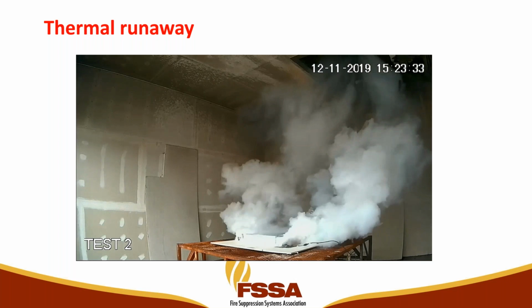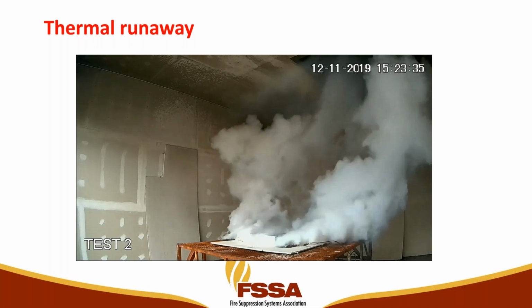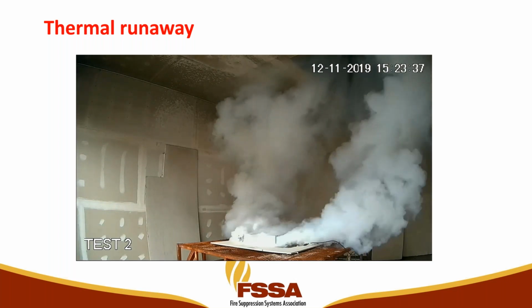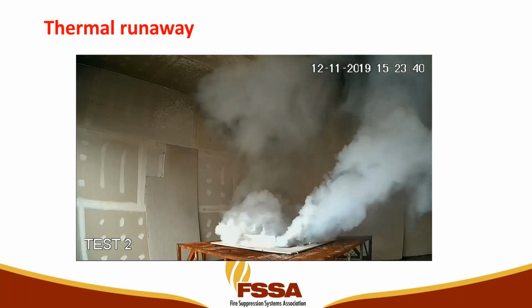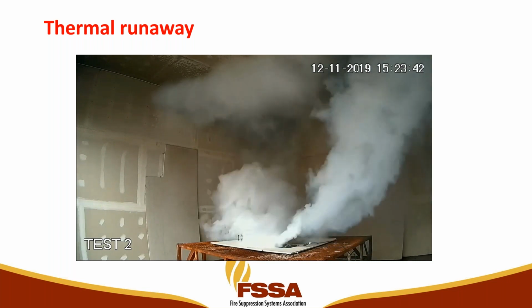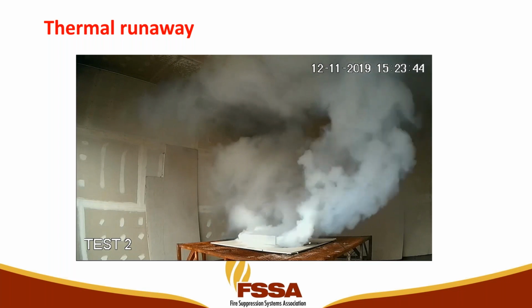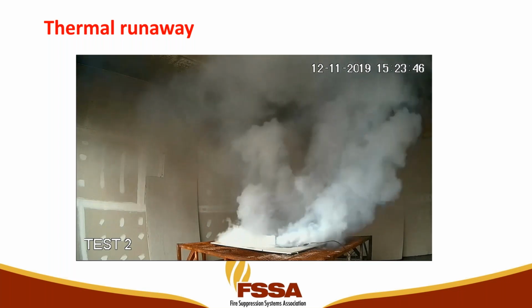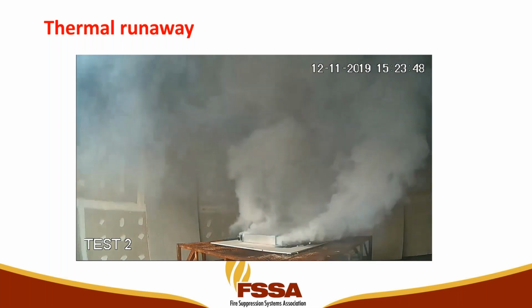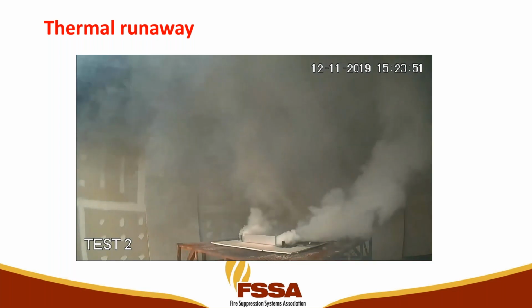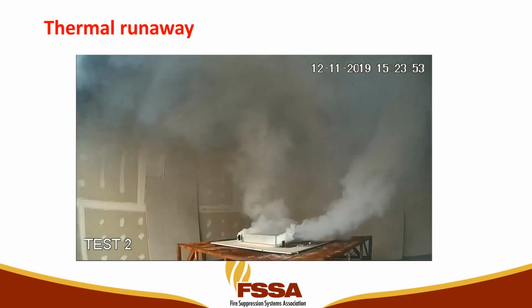But if you look at what's being produced there, there is no venting shown here, but there is a chimney in this test facility, so you can see a bit of the gases going out. In general, that's producing 30% hydrogen, 10% hydrocarbons. It didn't catch fire, but it is certainly filling the room.